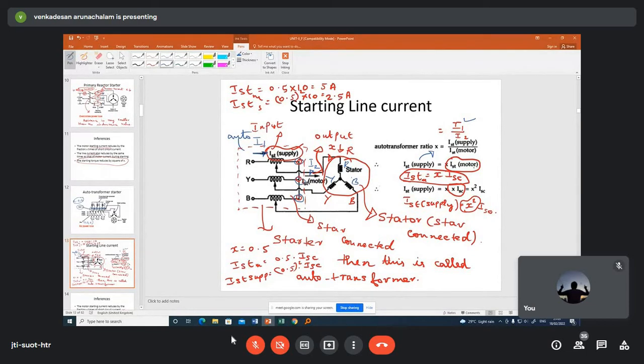And here, what is my ISC motor? ISC motor is nothing but X times your short circuit current. We have seen the derivation earlier. The starting current of the motor, if you use a starter, is X times the short circuit current. So you substitute ISC motor with X times ISC, and ISC supply becomes the square: X squared times the short circuit current.